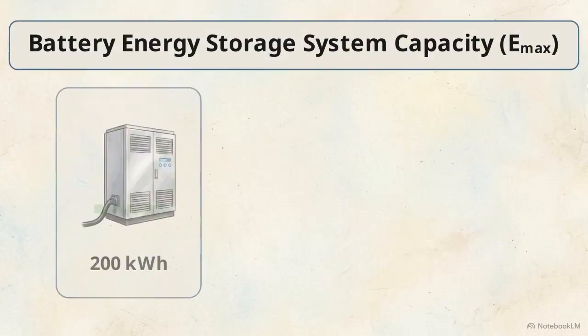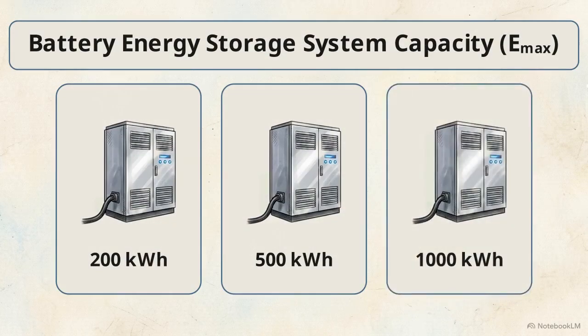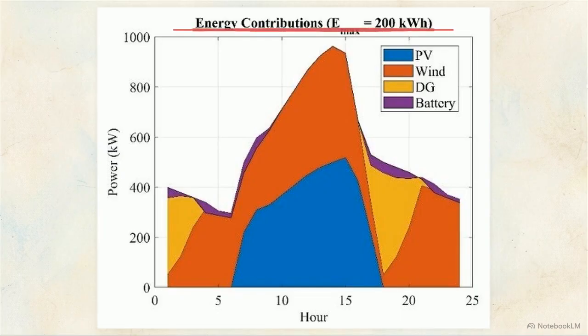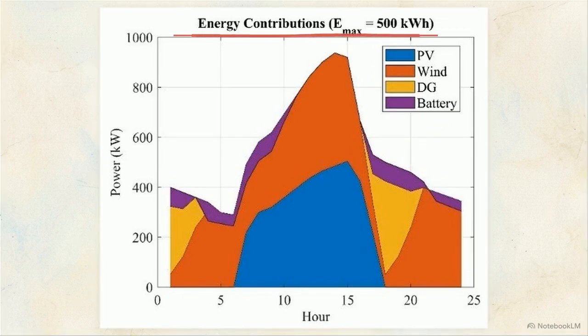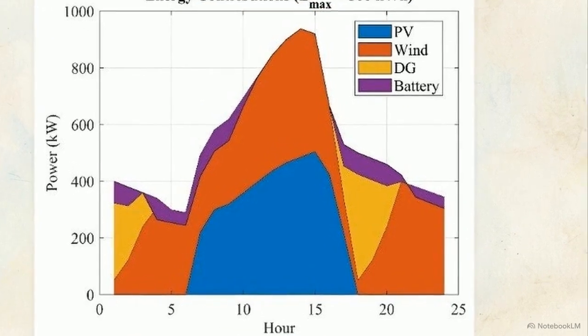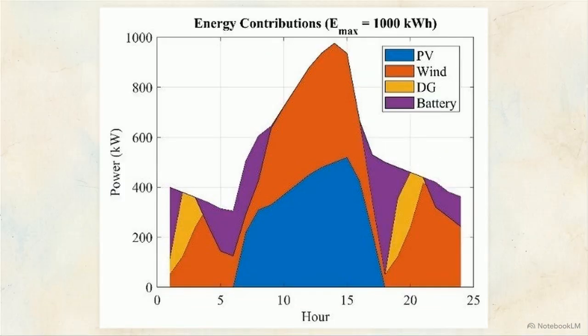To see how this algorithm handles different physical constraints, we can look at the raw dispatch data across 3 different battery capacities. This chart shows the hourly energy contribution using a small 200 kilowatt-hour battery. With limited storage, the battery cannot shift midday solar into the evening. This forces heavy reliance on the diesel generator during peak demand, seen in the large yellow section. This next chart shows the same system upgraded to a 500 kilowatt-hour battery. The larger capacity absorbs significantly more midday solar surplus, widening the purple battery discharge band and visibly flattening the yellow diesel requirement.